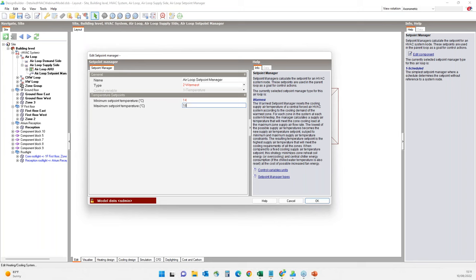This is a more optimal way to control the system instead of using a constant 14-degree temperature. With the 'warmest' option, the setpoint is set according to the cooling demand of the warmest zone — when there is no cooling demand the setpoint is 18 degrees, and when cooling is needed it actuates between 14 and 18, setting it to the highest level at which cooling demand could be met. Note that I'm using Design Builder in SI units mode; you can switch between SI and IP units in tools and program options.